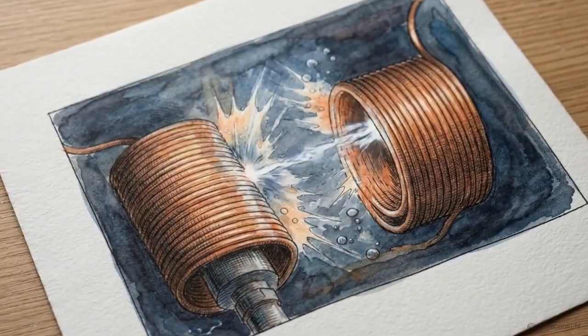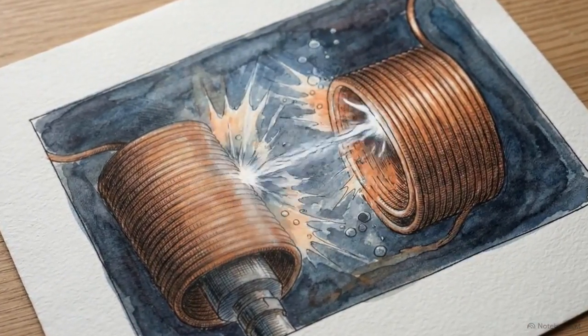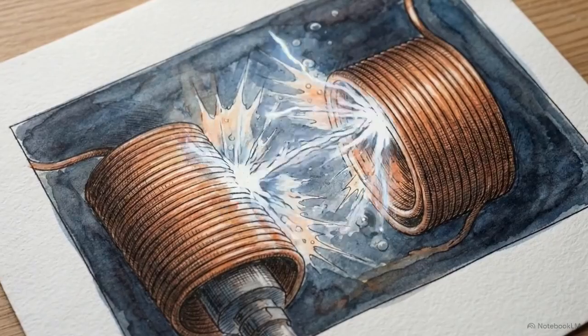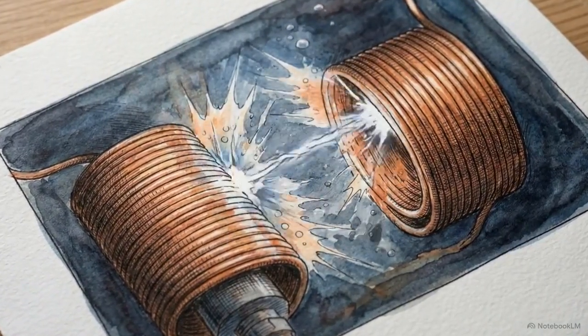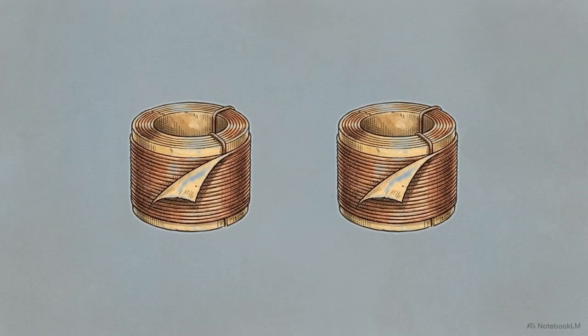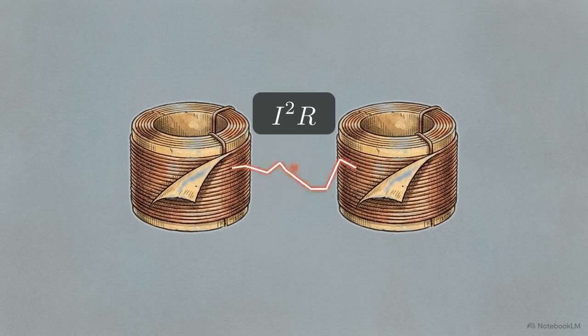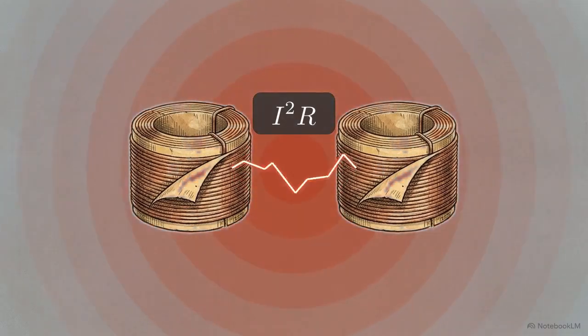The fault provides a path of least resistance, pulling an immediate, violent spike in current directly through the transformer's copper core. This animation of the transformer windings shows the immediate physical consequence of that fault. The heat generated within these coils expands according to the equation I squared R. Thermal stress does not scale linearly. It multiplies by the square of the fault current, turning electrical energy into destructive heat in milliseconds.